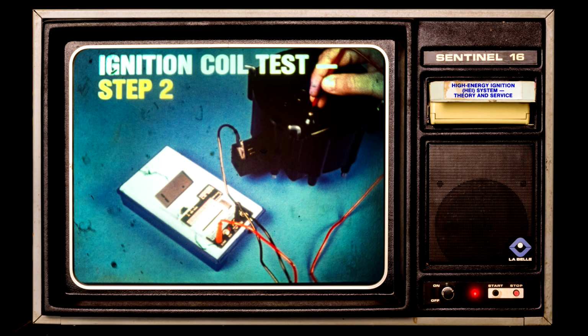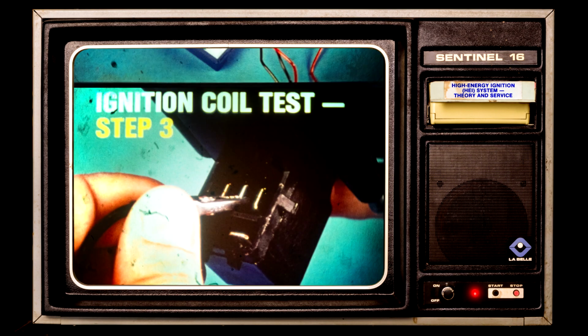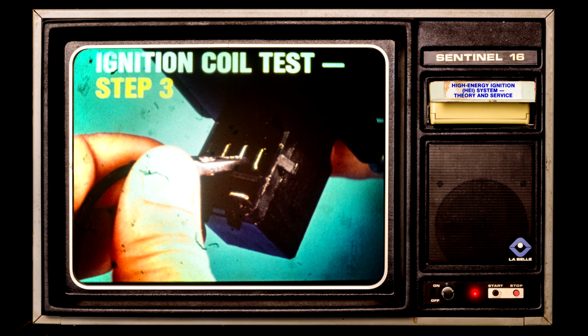Connect the ohm meter, as shown here, and take a reading. If this reading is not infinite, the coil should be replaced. Finally, connect the ohm meter as shown here and take another reading. If this reading is not infinite, the coil should be replaced.